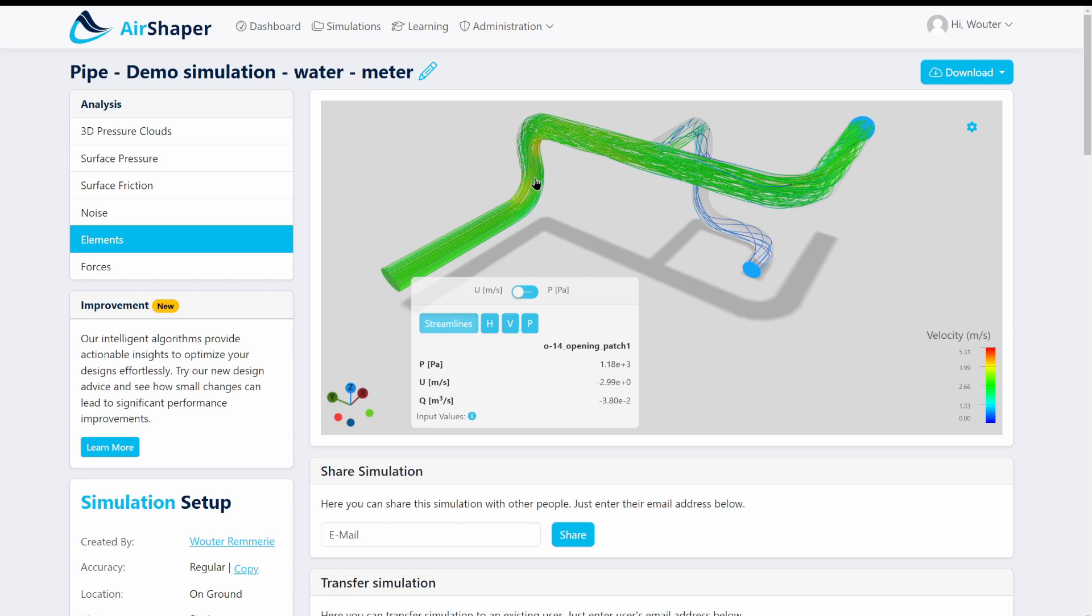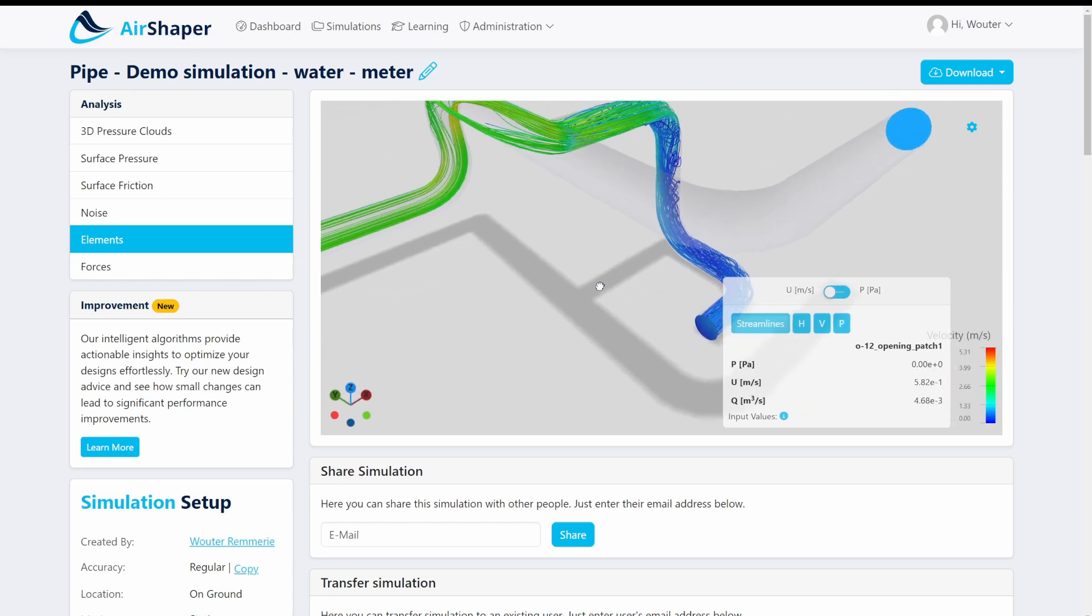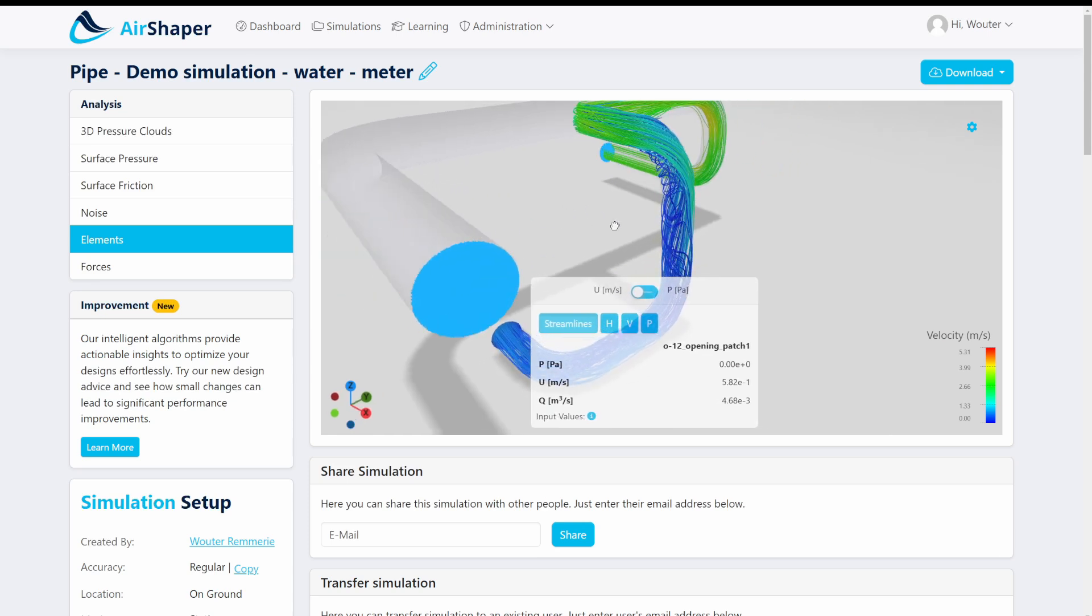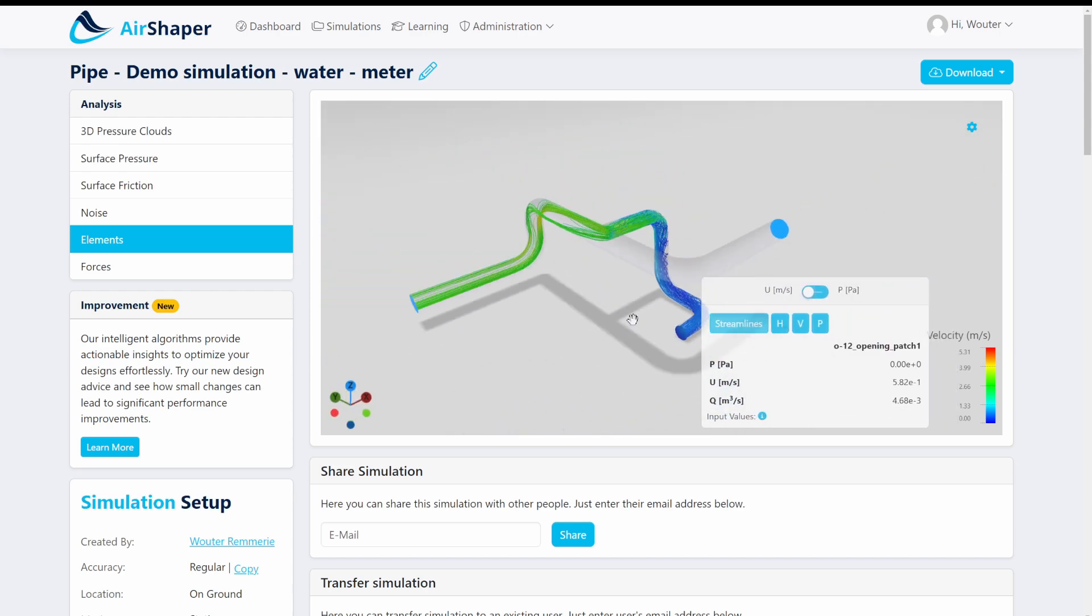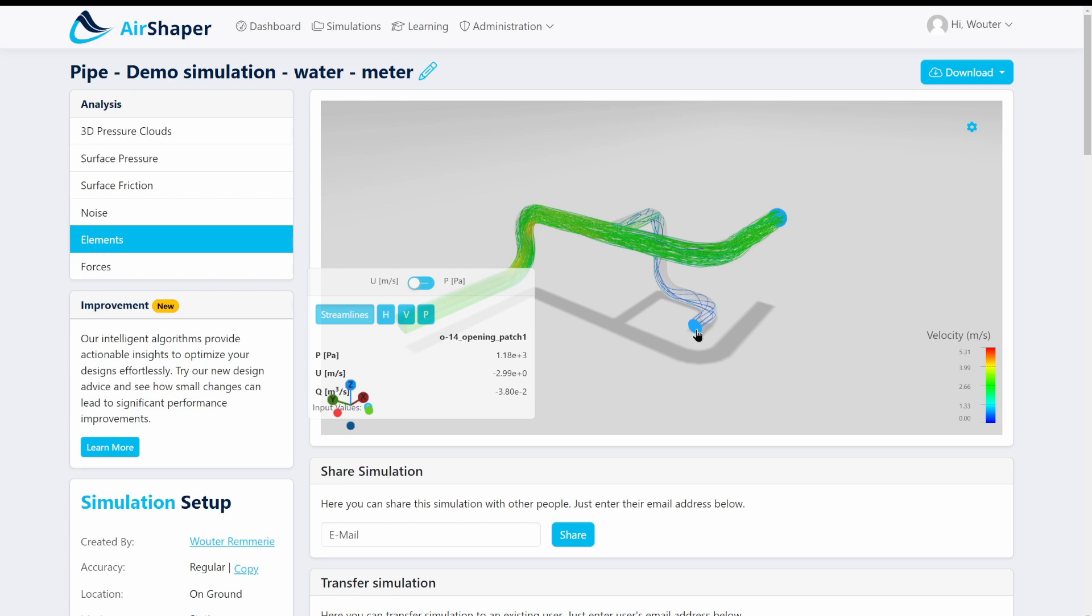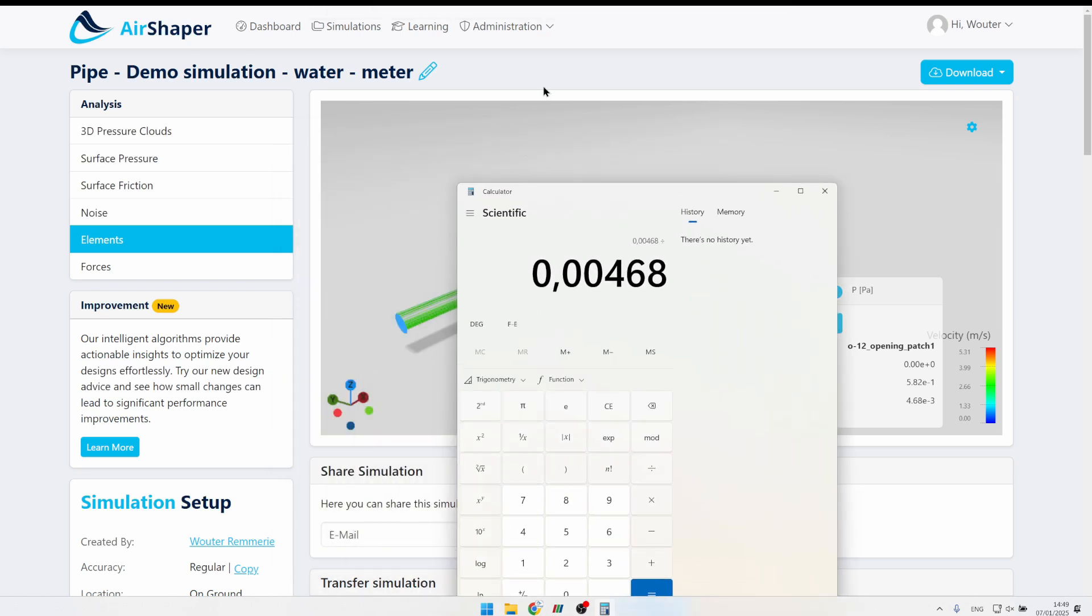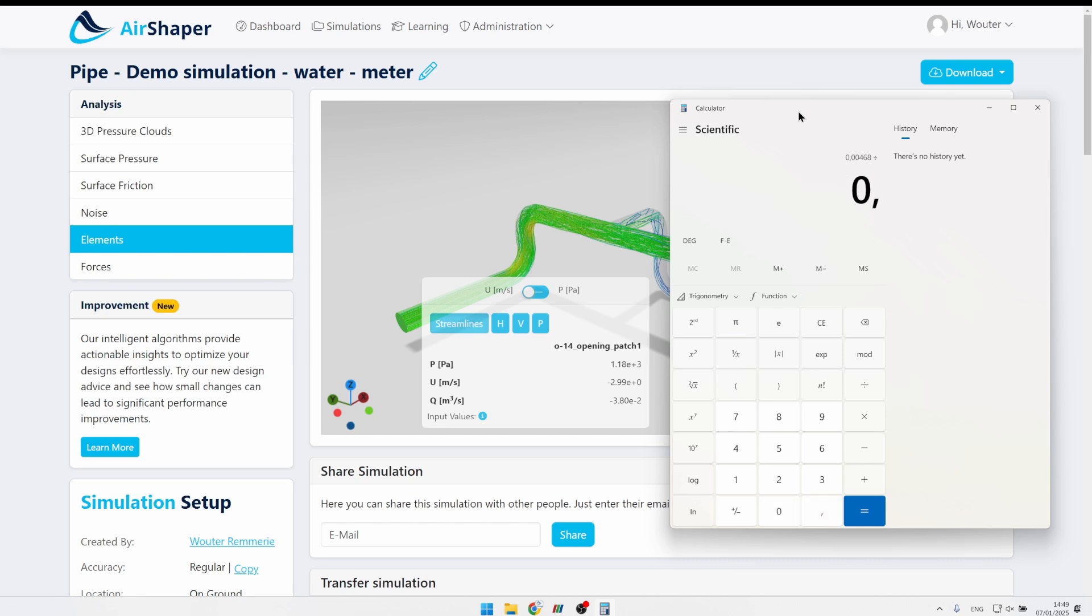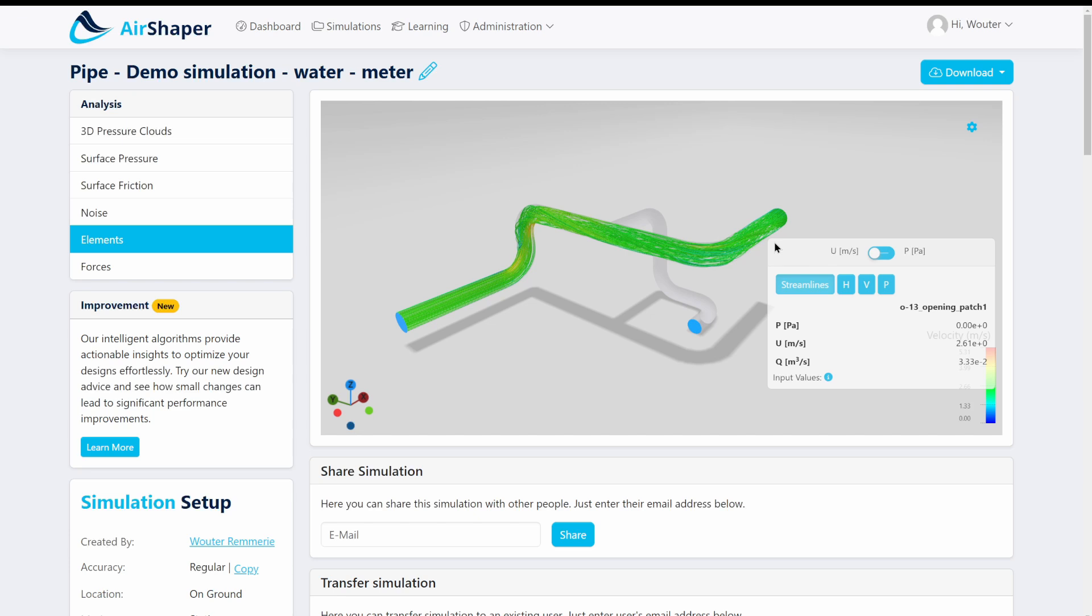This is whatever starts from the inlet if you want to see where the flow comes from you just click the outlet and then you can see that the flow going out of this side branch which is also slightly smaller in diameter gets far less flow and the flow velocity is much lower here. So if you look at the inlet we had a velocity specified which translates into a flow rate of 0.038 cubic meters per second and 0.00468 of that is going into this side branch. So if you divide that, so we have 0.00468 divided by 0.038, that means only 12% of the flow is going out via this channel and all the rest of the flow is going via the main branch.